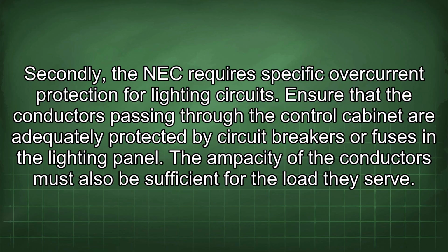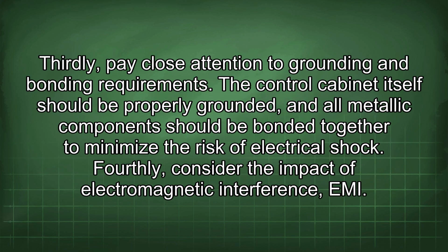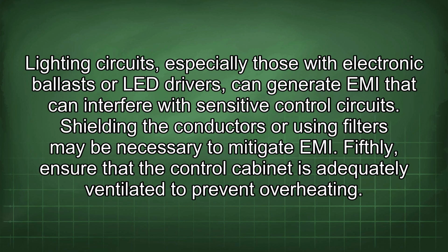Secondly, the NEC requires specific overcurrent protection for lighting circuits. Ensure that the conductors passing through the control cabinet are adequately protected by circuit breakers or fuses in the lighting panel. The ampacity of the conductors must also be sufficient for the load they serve. Thirdly, pay close attention to grounding and bonding requirements. The control cabinet itself should be properly grounded, and all metallic components should be bonded together to minimize the risk of electrical shock. Fourthly, consider the impact of electromagnetic interference, EMI. Lighting circuits, especially those with electronic ballasts or LED drivers, can generate EMI that can interfere with sensitive control circuits. Shielding the conductors or using filters may be necessary to mitigate EMI.